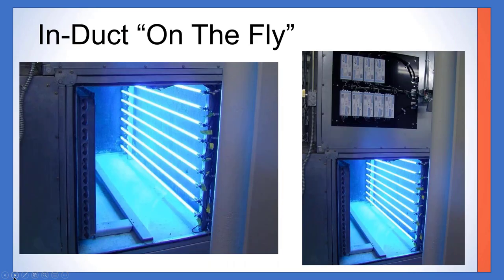As I mentioned earlier, in-duct on-the-fly requires tighter spacing. This particular job is at Lackland Air Force Base, with 160 air handling units, where this system was designed for a 99.98% first-pass kill of tuberculosis, a harder microbe to kill than the coronavirus.